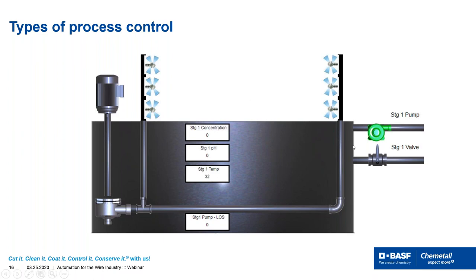You'll notice the pump is turned green in this picture, meaning chemical feed has taken place. If the valve was green, it may be blowing down, allowing some of the chemistry in that tank to drain because the solids are too high. These are the kind of things you'd want to look for when looking at process control for your system. This is one way of doing it.